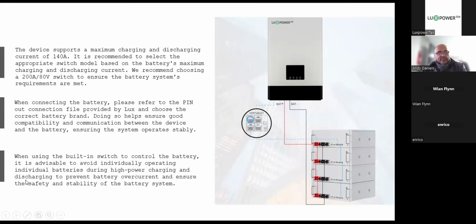All right, when using the built-in switch to control the battery, it's advisable to avoid operating individual batteries during high power charging and discharging to prevent overcurrent. Okay, so basically what we mean by that is do not switch your batteries on and off individually if the inverter is either discharging or charging the batteries, because there's high current flowing through these cables. And especially if you're pulling fuses, that's a very big spark that you're going to have to control. So always make sure that your inverter is in standby mode and the batteries are neither being charged or discharged before you make and break connection. Okay.